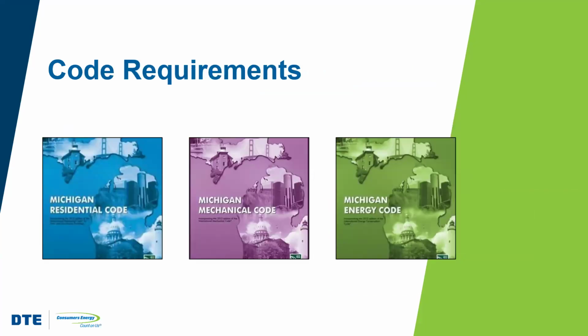There are many code requirements for these systems. And we'll talk a little bit about some of those criteria now. One of the biggest things, though, is test pressure. These piping systems need to be hydrostatically tested to make sure that the piping can withstand the pressures expected in the system, and then pressures in excess of what's expected in the system to provide additional assurance against catastrophic failure. Right, so in general, we're going to be testing at pressures that are 1.5 times the maximum design pressure, and we're going to pressurize that pipe, and then we're going to hold that pressure for between 15 and 20 minutes, and we want to make sure that there are no leaks, and if there are any leaks, we're going to repair them. The pressures differ, for example, for a radiant floor system or for a ground source heat pump system. There we want the test pressure to be 100 psi.